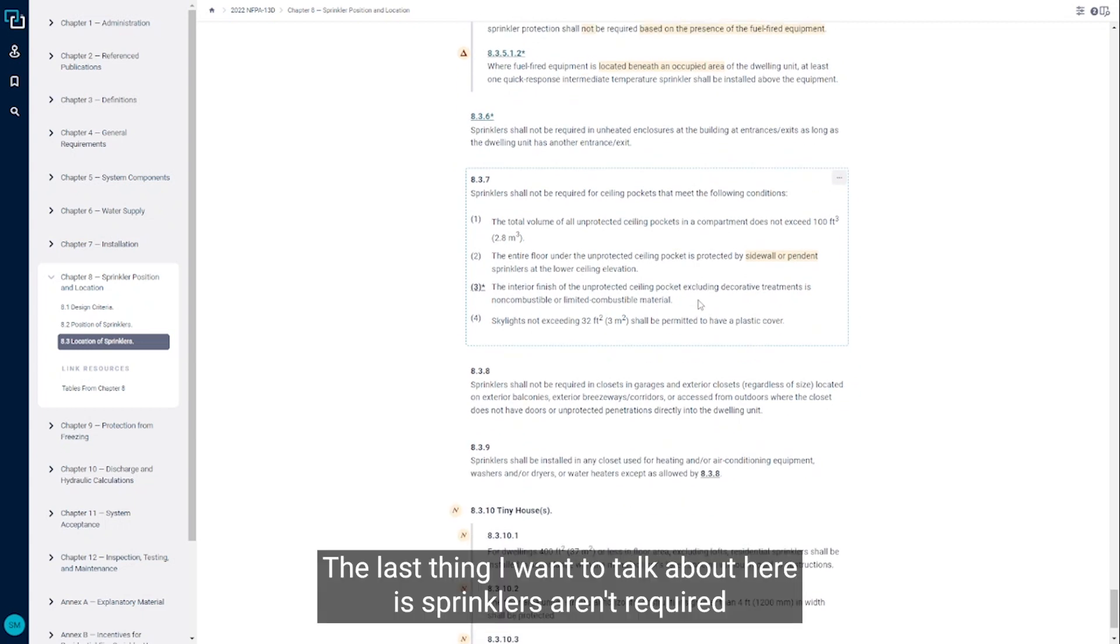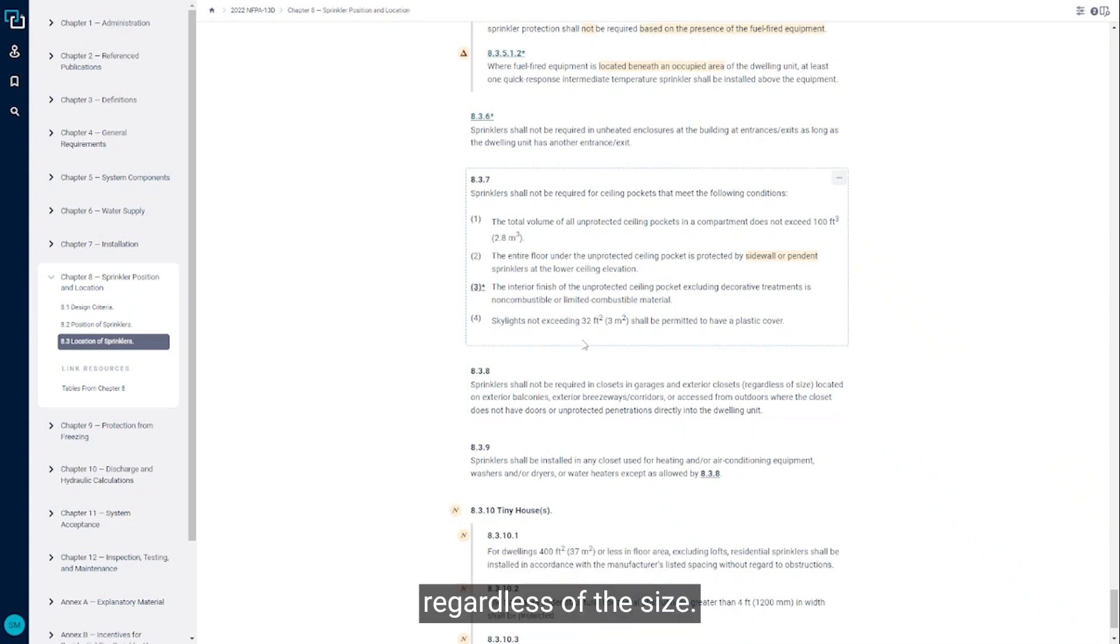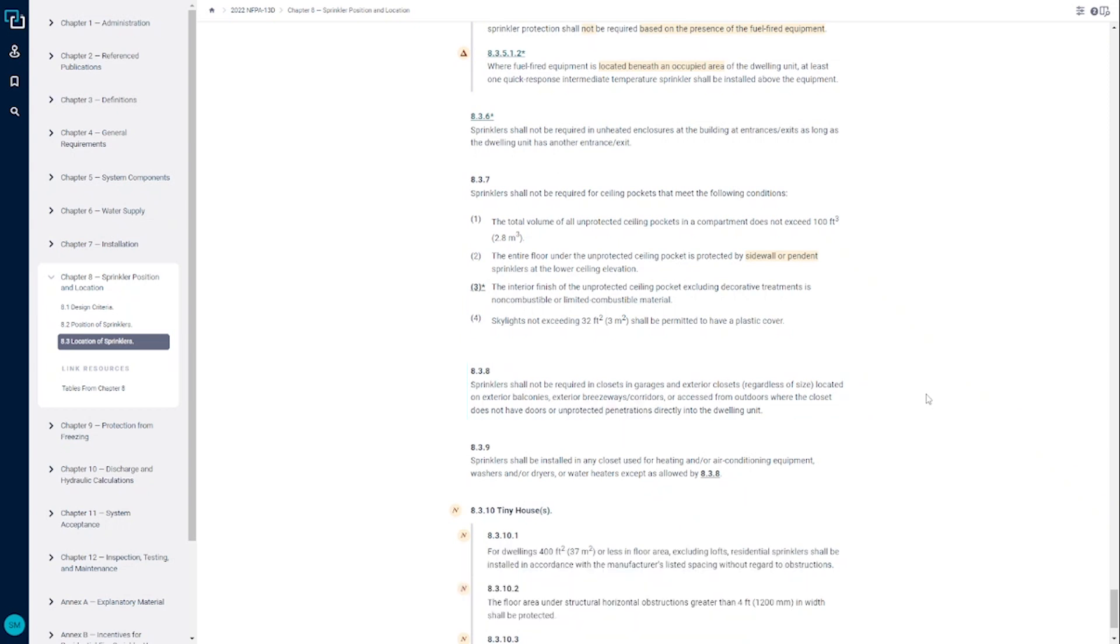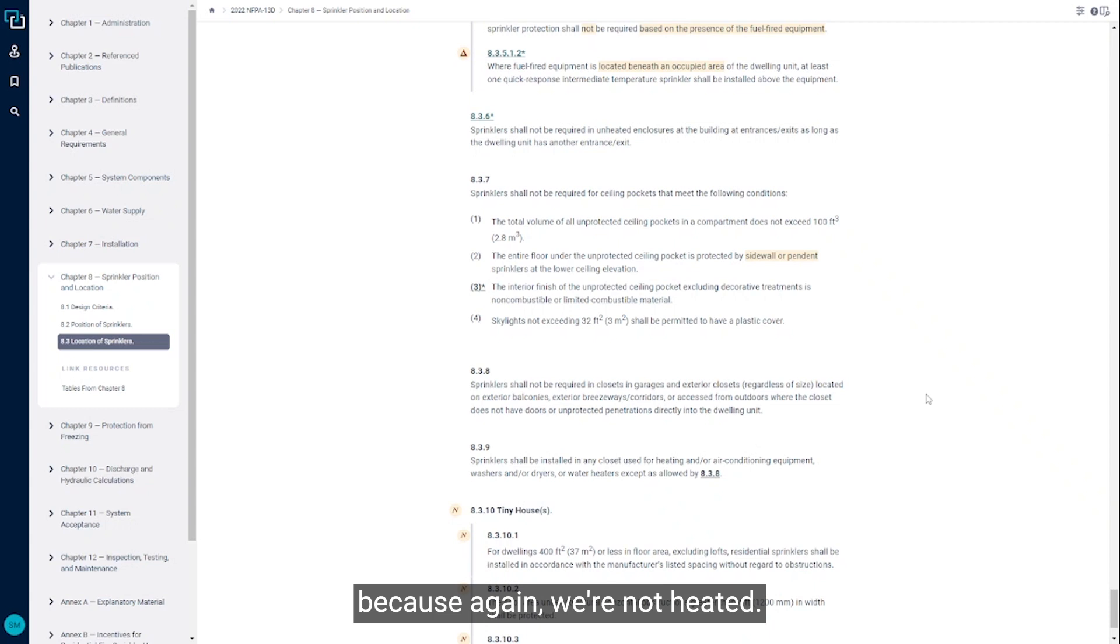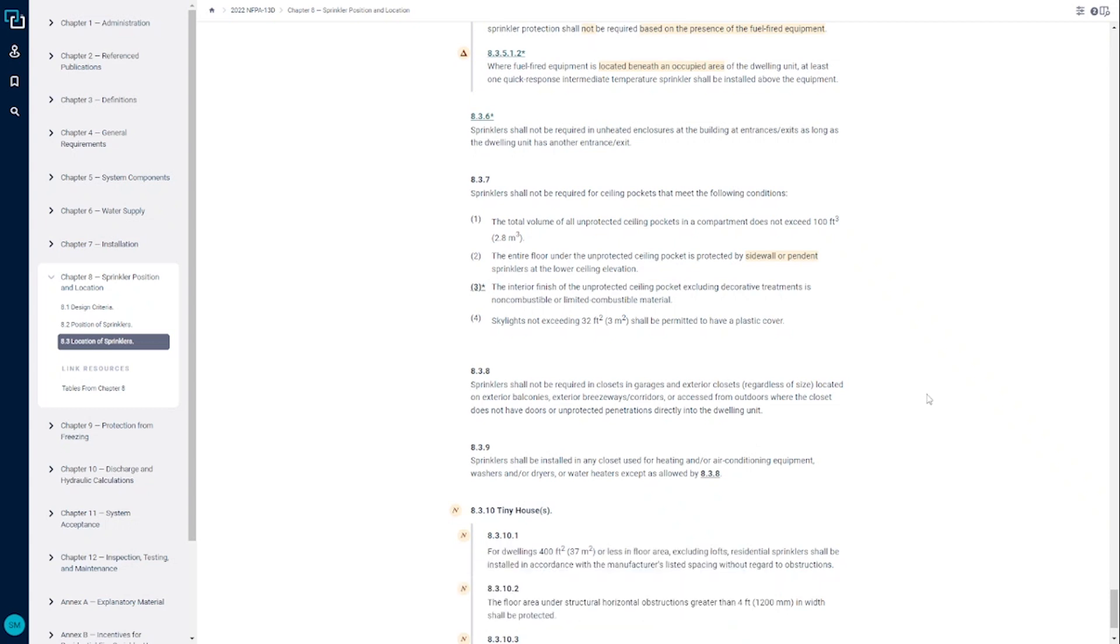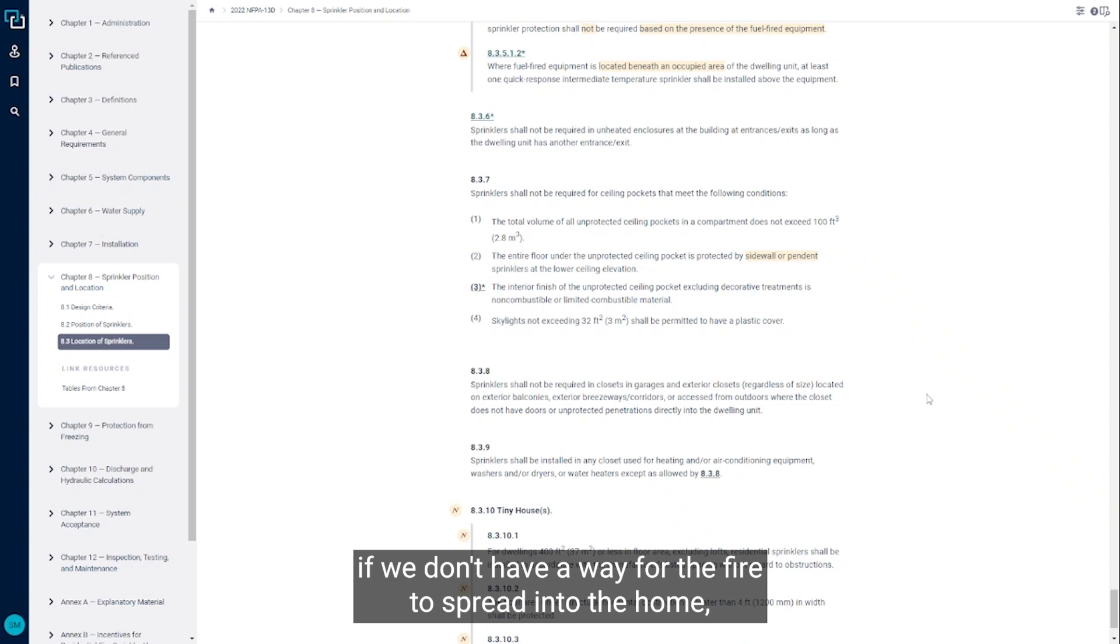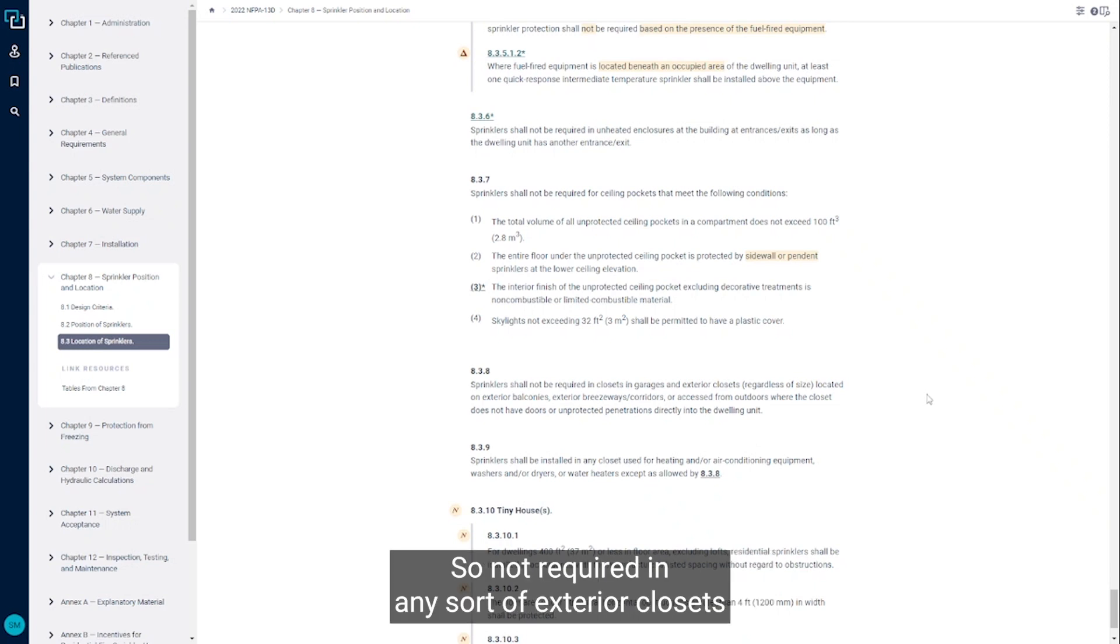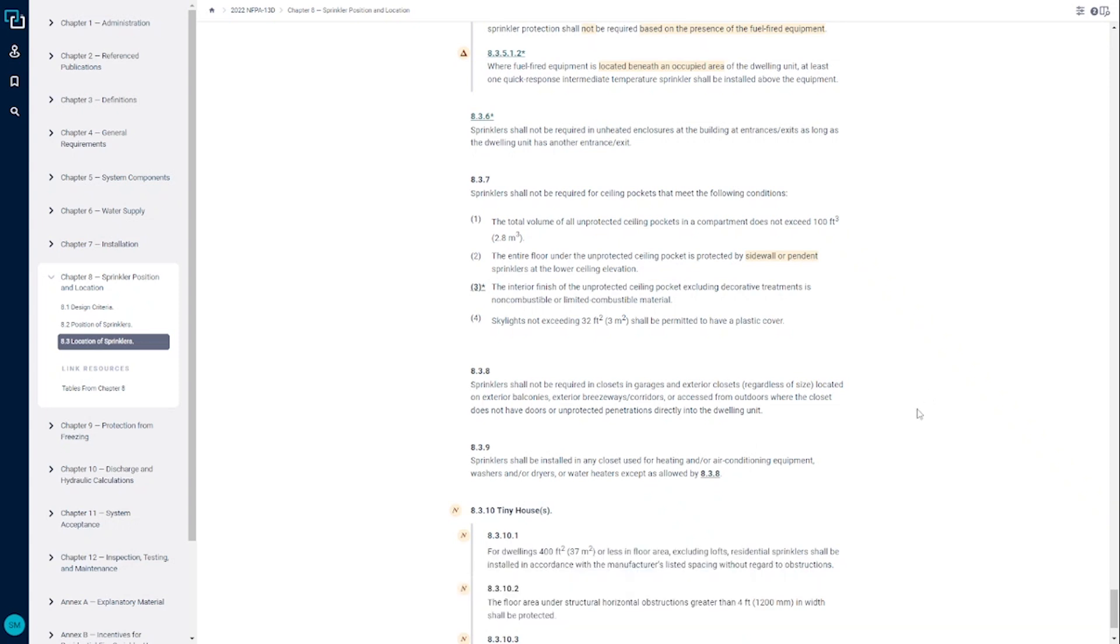The last thing I'm going to talk about here is sprinklers aren't required in closets in garages or exterior closets, regardless of the size. This is important: provided here that there's no unprotected penetrations directly into the dwelling unit, we aren't required to have sprinkler protection there because they're not heated, so we would have had to provide some sort of freeze protection, and the cost would be significantly high. If we don't have a way for the fire to spread into the home, we see that there's a relatively low chance of loss of life if a fire were to start in that sort of space. So not required in any sort of exterior closets or closets within a garage.